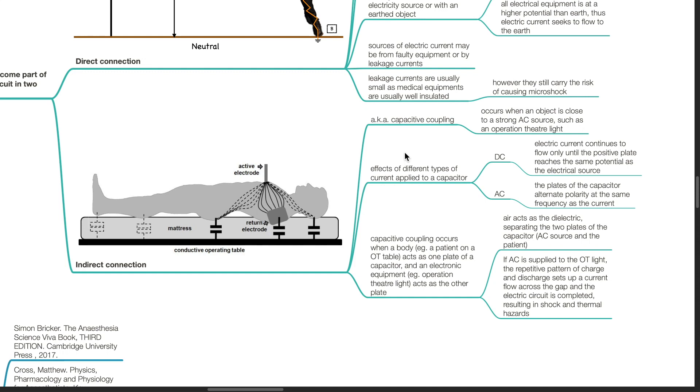Capacitive coupling occurs when a body, such as a patient on the OR table, acts as one plate of a capacitor and electrical equipment, such as an operation theater light, acts as the other plate. Air acts as the dielectric separating the two plates. If AC is applied to the OT light, the repetitive pattern of charge and discharge sets up a current flow across the gap and the electric circuit is completed, resulting in shock and thermal hazards.